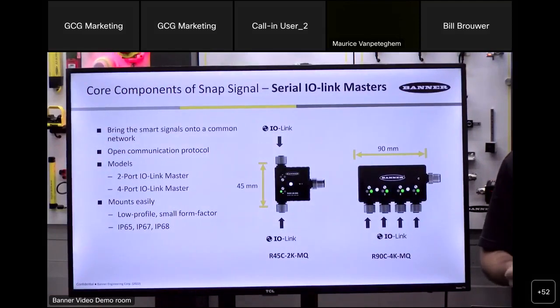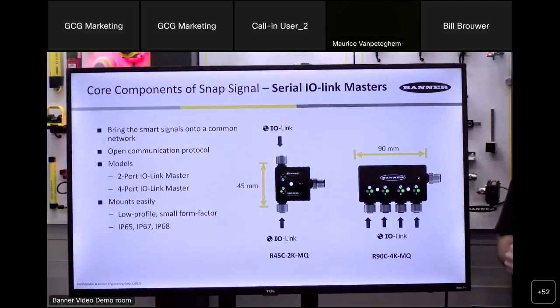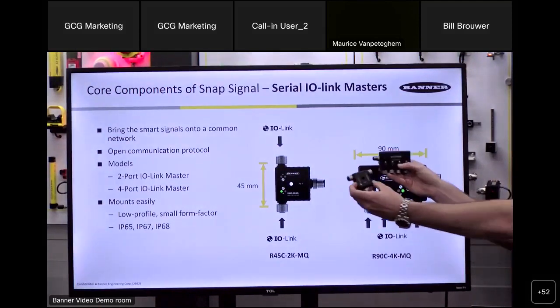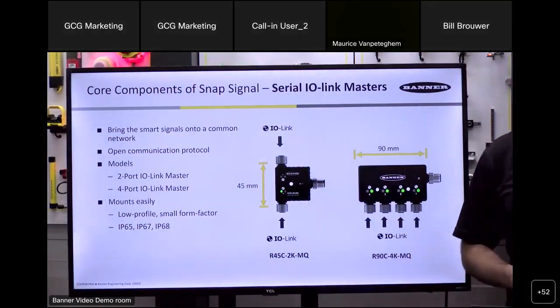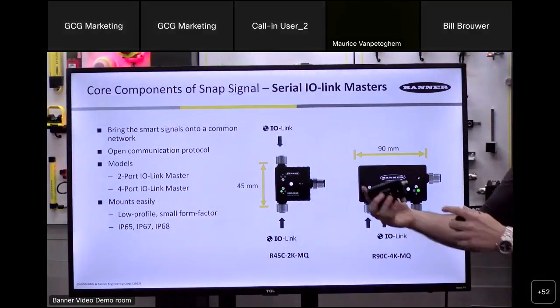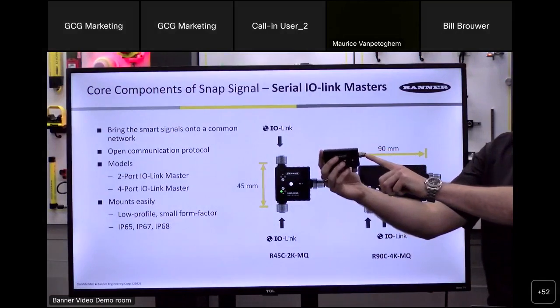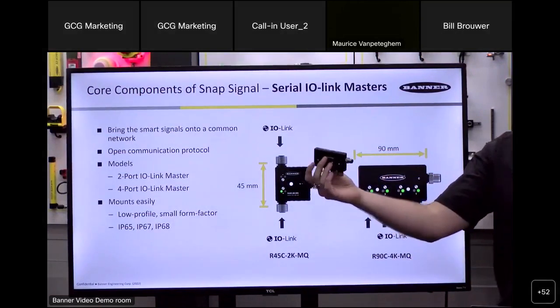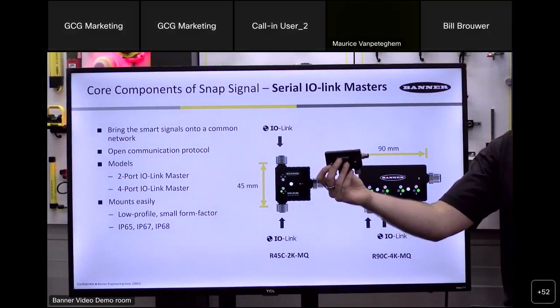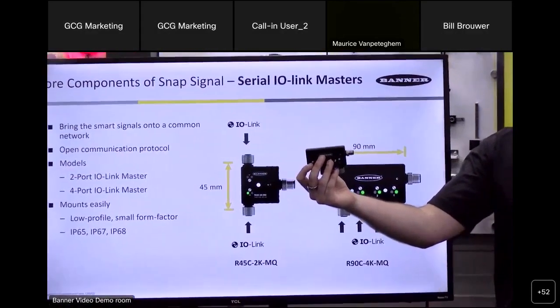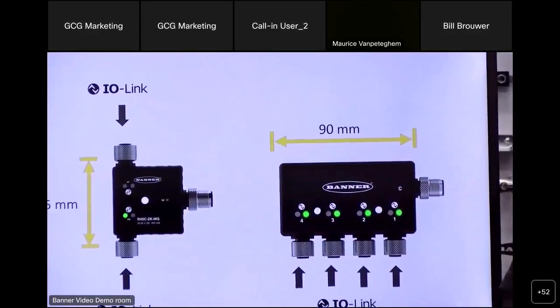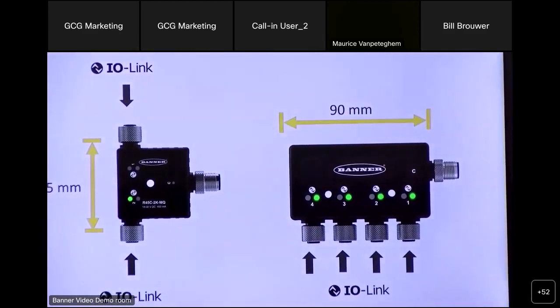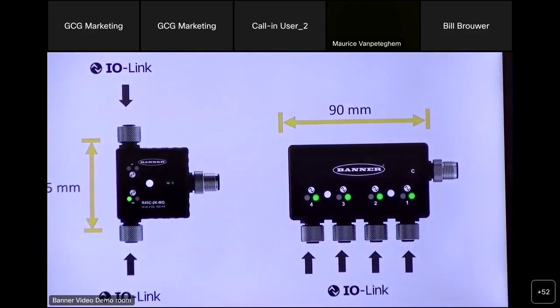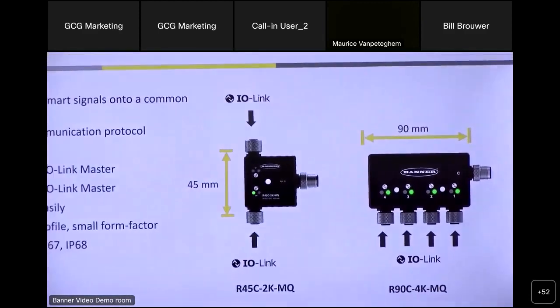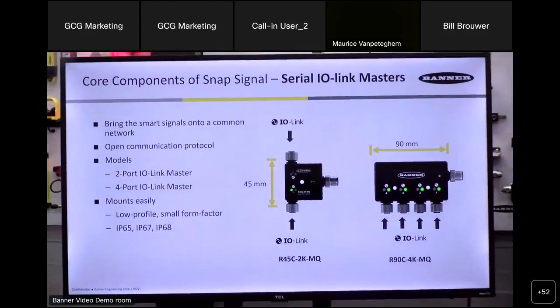IO-Link is a consortium. There's well over a couple hundred manufacturers that have IO-Link devices. And with these two IO-Link devices that we see right here, we're able to capture that IO-Link data and send that data out via RS-485 protocol back to the DXMR90 industrial controller. So we're able to capture data from just about any IO-Link sensor. And so this has many different advantages. And people see Modbus RTU or RS-485 protocols and say, well, why not Ethernet?